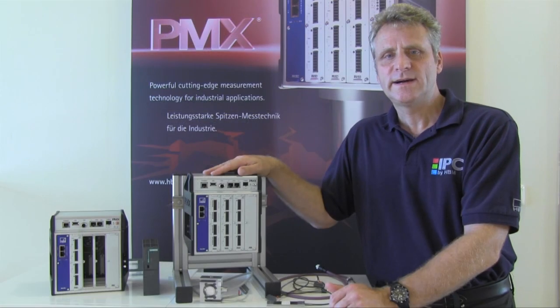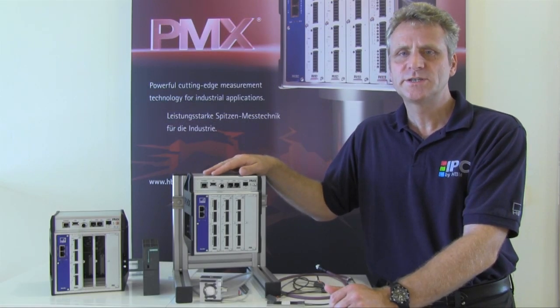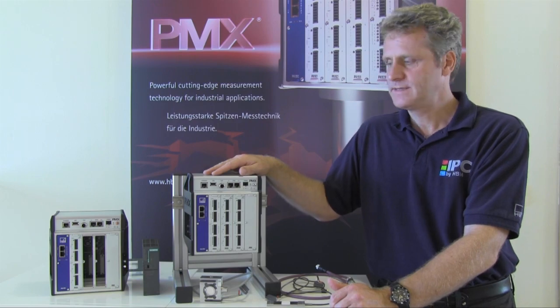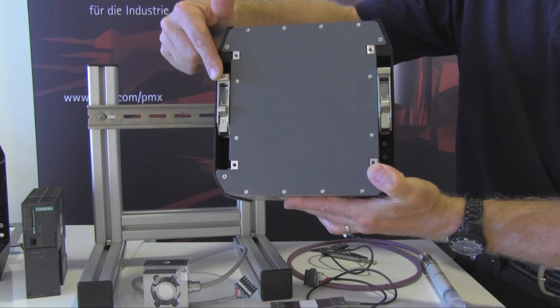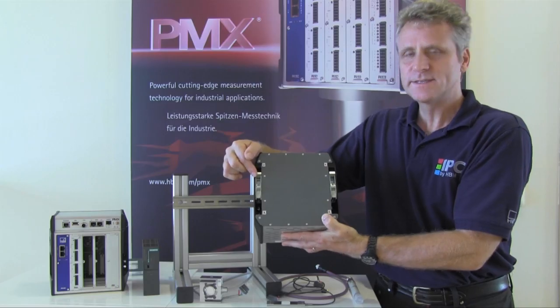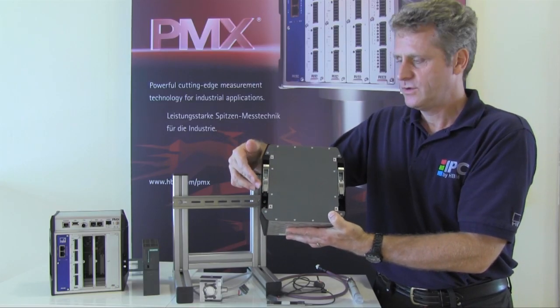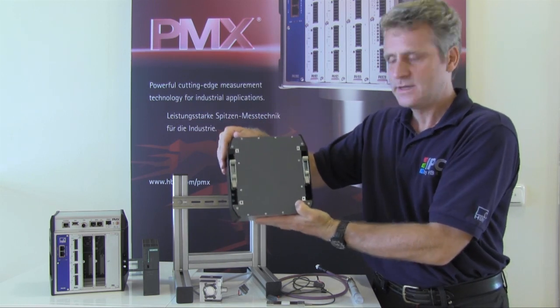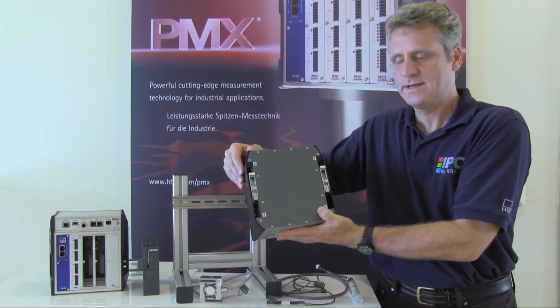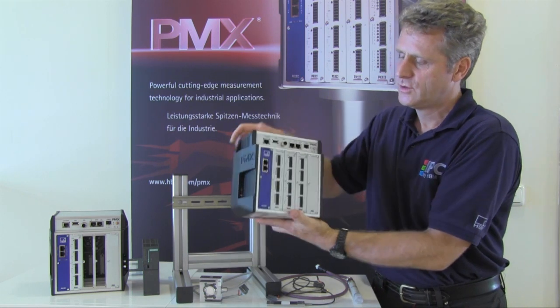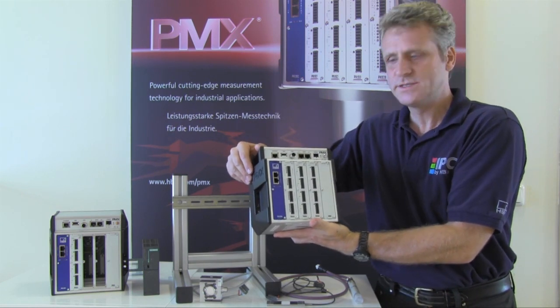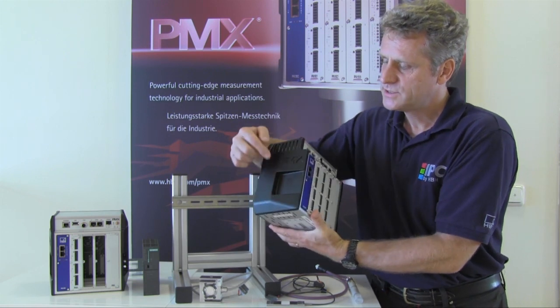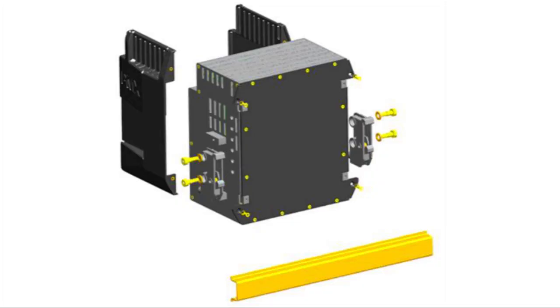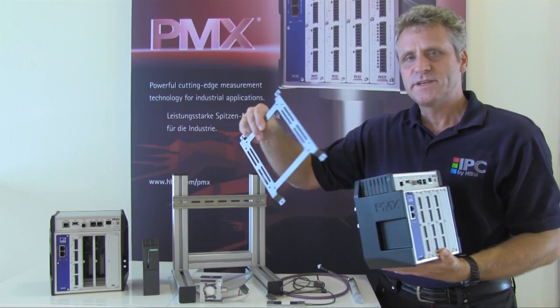The measuring amplifier can be mounted two different ways: on a mounting rail, in control cabinets, or directly on the wall. We have mounts on the back of the device for mounting on routing rails. They can be used to adjust the height. This ensures optimum adjustment of the mounting height later in the control cabinet. To fasten the measuring amplifier securely and reliably onto the mounting rail, the device can also be permanently mounted on the mounting rail with two Allen screws after assembly.